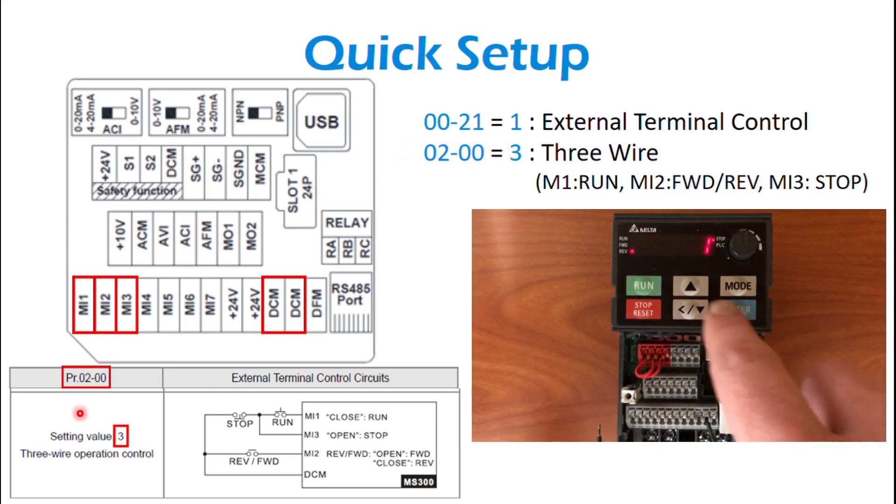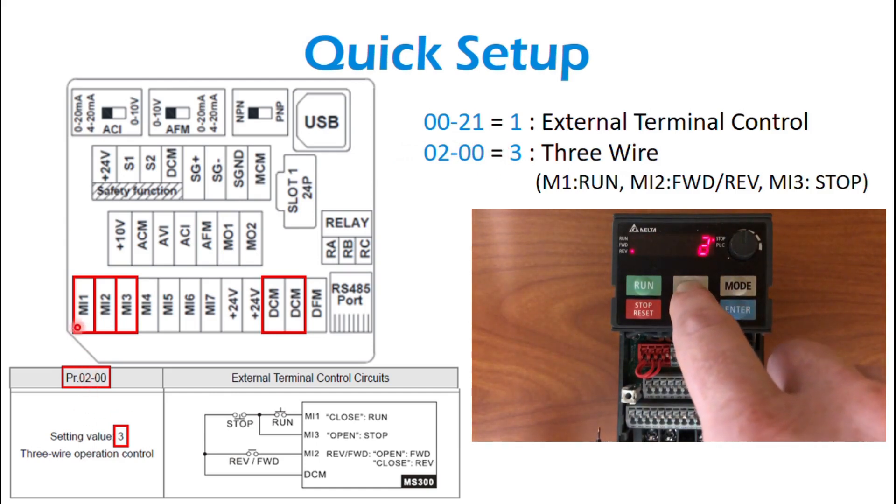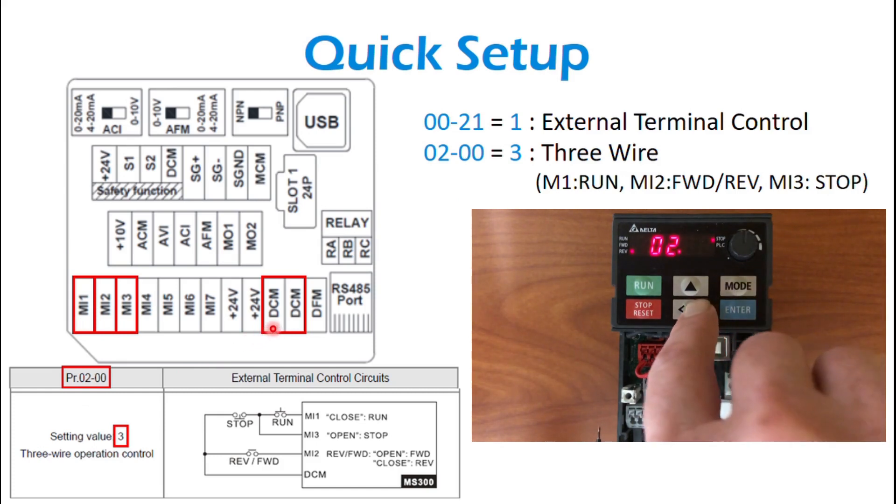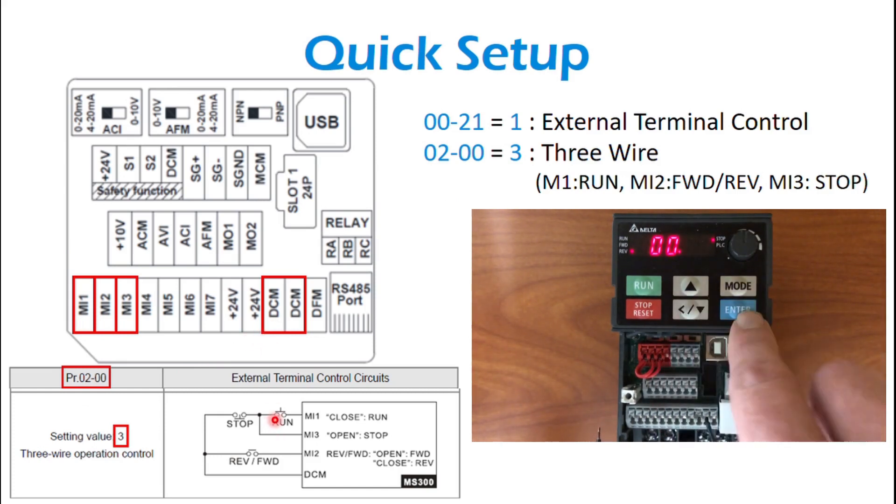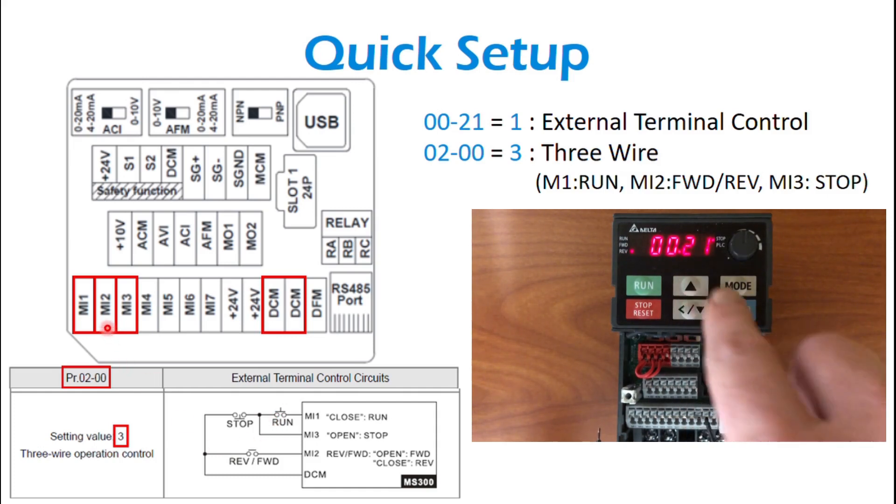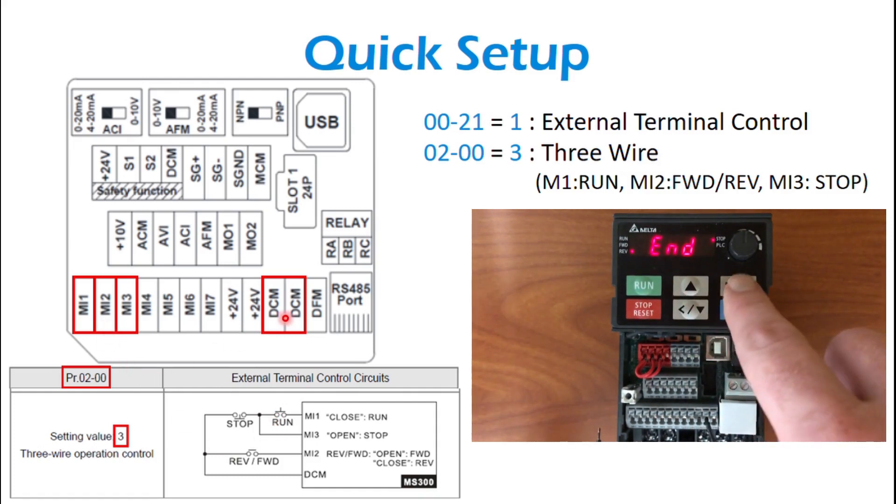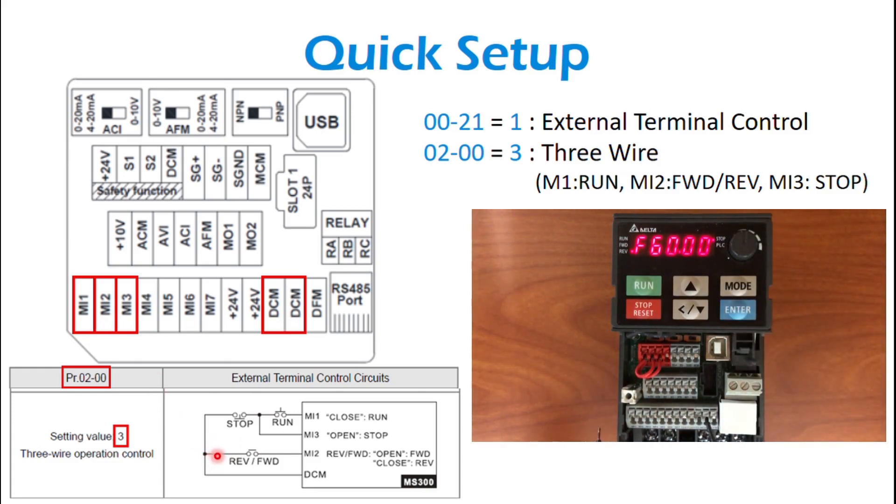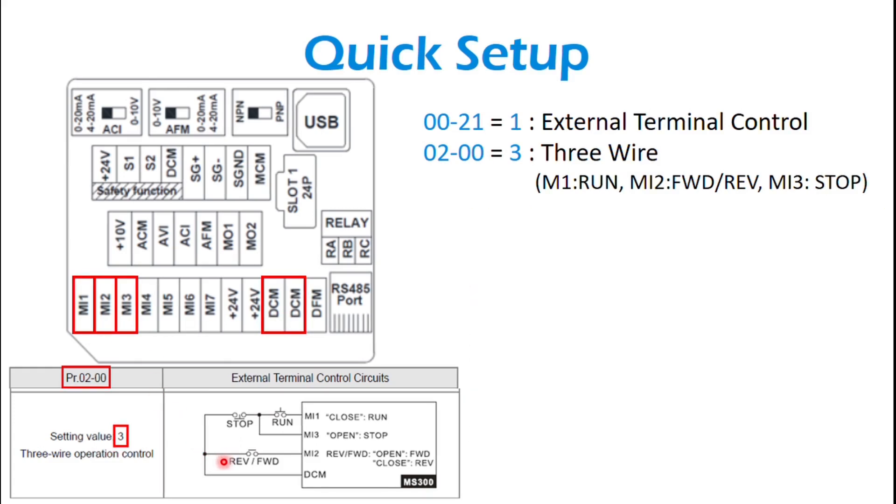And then you have MI1 to DCM is a momentary push button run signal. MI2 to DCM, if you're using a direction control, it's a maintained dry contact direction forward or reverse control. If that's open, it's forward.